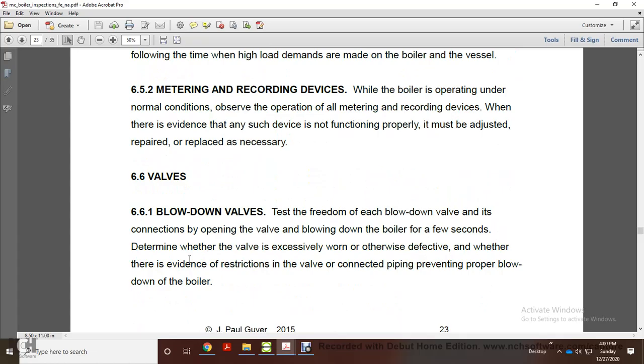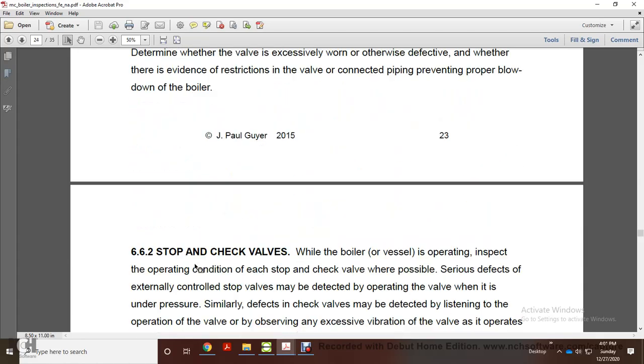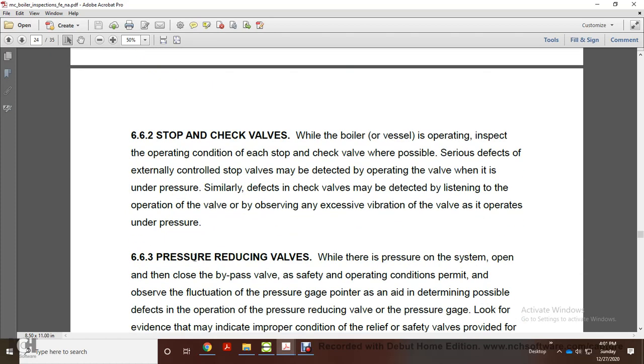661, blow down valve. Test the freedom of each blow down valve by opening the valve and blowing down the boiler for a few seconds to determine whether the valve is excessively worn or otherwise defective, and whether there is evidence of restriction in the valve connection preventing the blow down of the boiler. Stop check valves. While the boiler or vessel is operating, inspect the operating condition of each of the stop and check valves. A possible serious defect with externally controlled stop valves may be detected by the operation of the valve when it is under pressure.